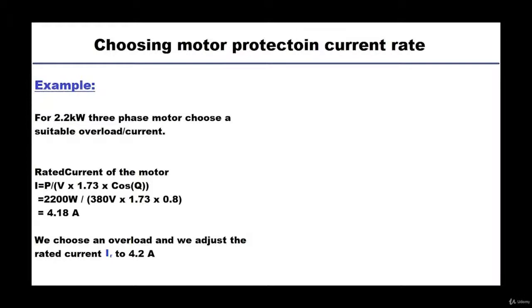And because of the thermal characteristics, we have accounted for the inrush current, because the thermal characteristic, as we mentioned, would take around 3, 4, or 5 seconds to take action, which is enough time for the inrush current to pass. So we need to adjust it exactly at the motor rated current.